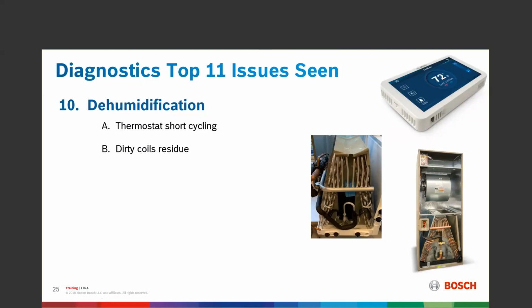Try cleaning the coil. We've had a couple cases where on horizontal applications, water may drip off the coil into the bottom of the pan, not in the condensate pan, but under the bottom of the panel, and cause condensation on the outside. That's been an issue with dirt. Airflow issues. If I exceed 500 foot per minute velocity across the coil, I will wick water off my coil. Having the proper airflow and proper duct size is very critical to keep that velocity below 500 foot per minute.